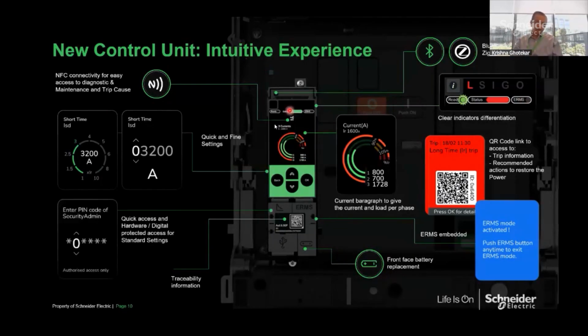Of course, for the protection settings, you can go through this tab, or if you want to directly access the protection setting, you can open this flap and press the button inside this flap, and it will go to the IDMTL curve or the overload, short circuit and instantaneous or ground fault protections, depending on the type of trip unit. Now, there can be a requirement that for these protections you want to avoid unauthorized access. Of course there is a latch, you can put a padlock, or there is another option, you can put a user defined 6-digit password so that everyone can monitor it, but if you want to change it, you need that particular password. That provision is also available.